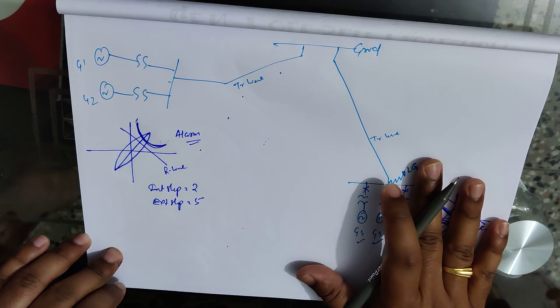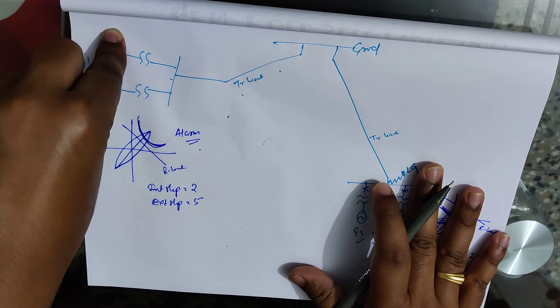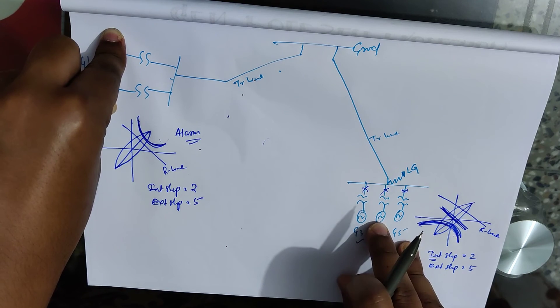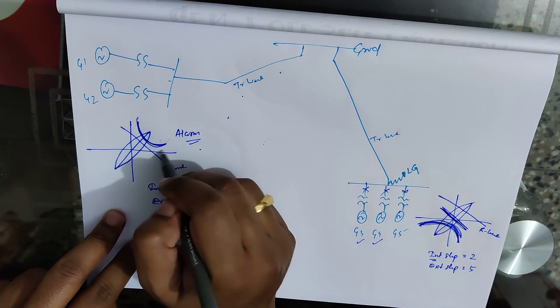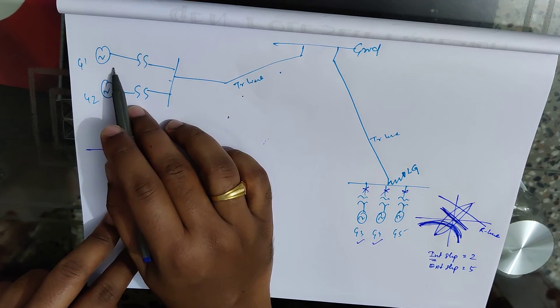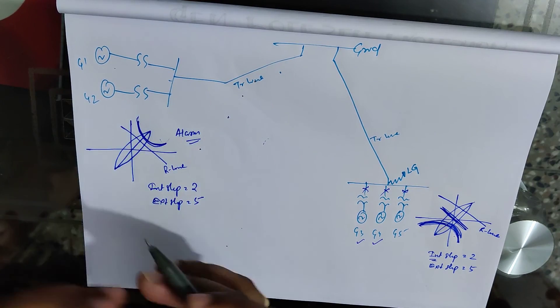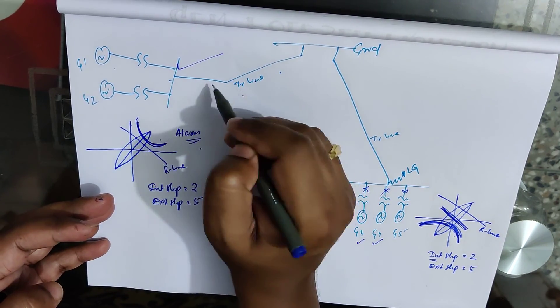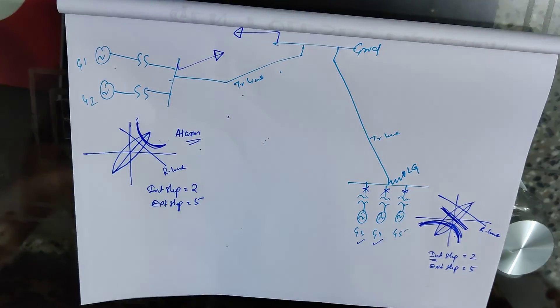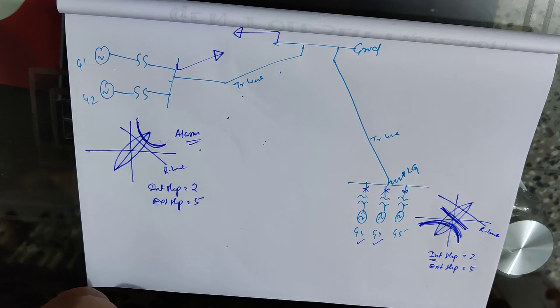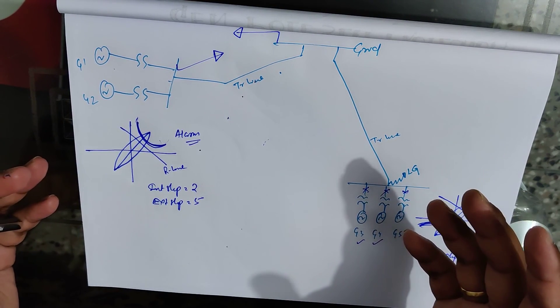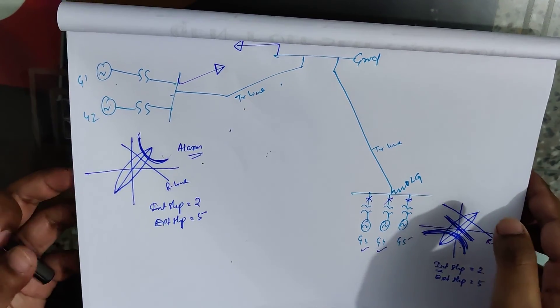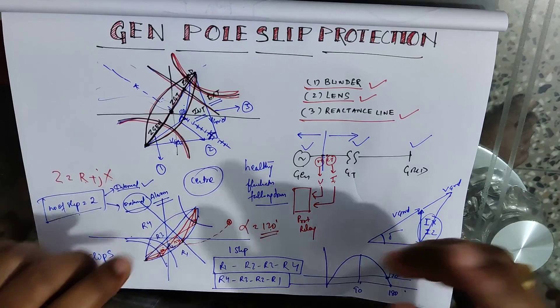These generators trip to safeguard the adjacent generators, because if they do not trip, the external swings will eventually create problems at the other station, disturbing the frequency of adjacent drives in the power plant and all consumers connected to the grid. This is a very critical protection. I hope this explanation of pole slip protection — its phenomenon and characteristic — has been helpful. Thank you and have a nice day.